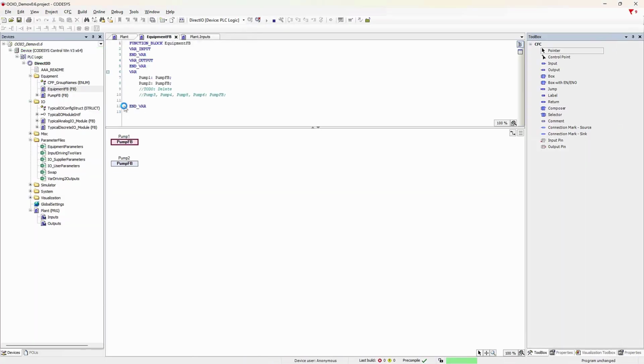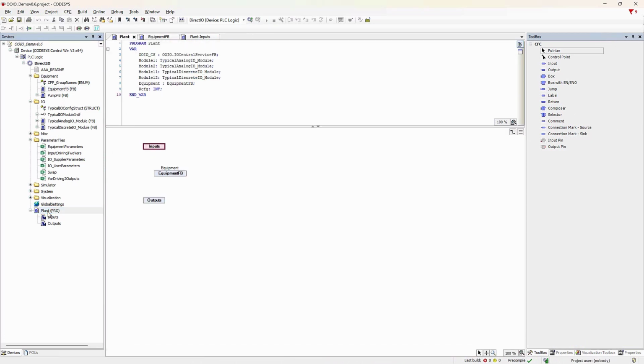So just to reiterate, at any time we could go back to the program, add more pumps and I/O modules, and activate them in an online change. It's that easy. No need to shut down the plant or the factory, or do a restart, or do a new download. Then we can manually map that new I/O, or update and read in the I/O mapping file, and the new pump and the new I/O modules are fully functioning and ready to roll. Life is so much simpler without the CODESYS I/O tree.